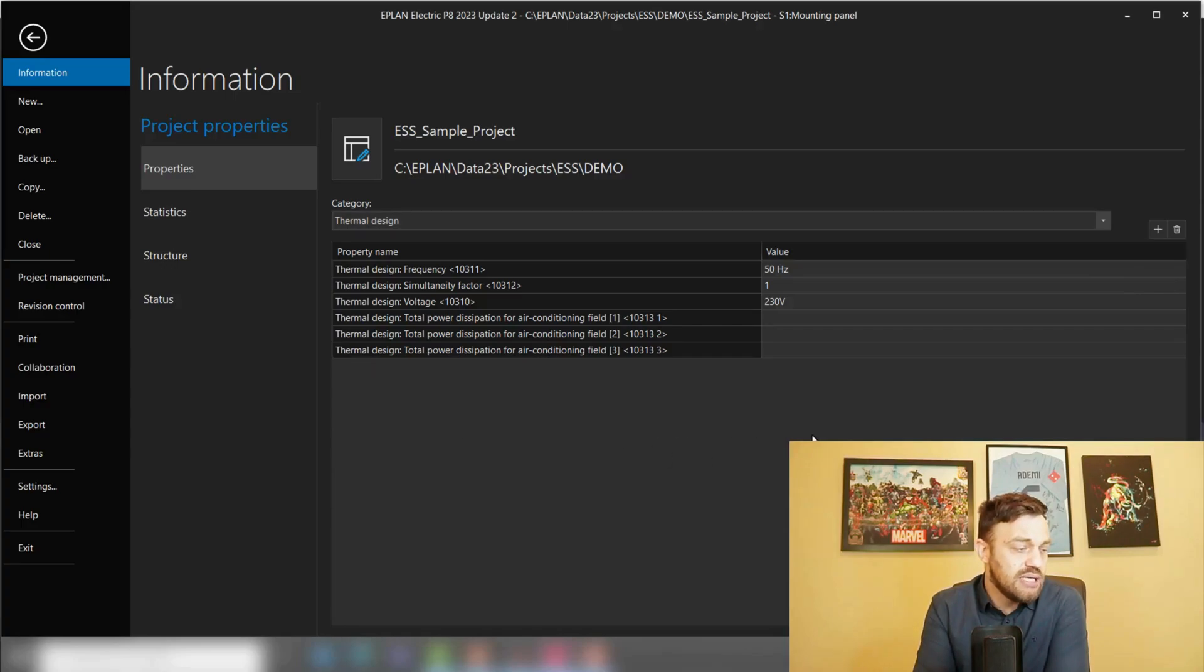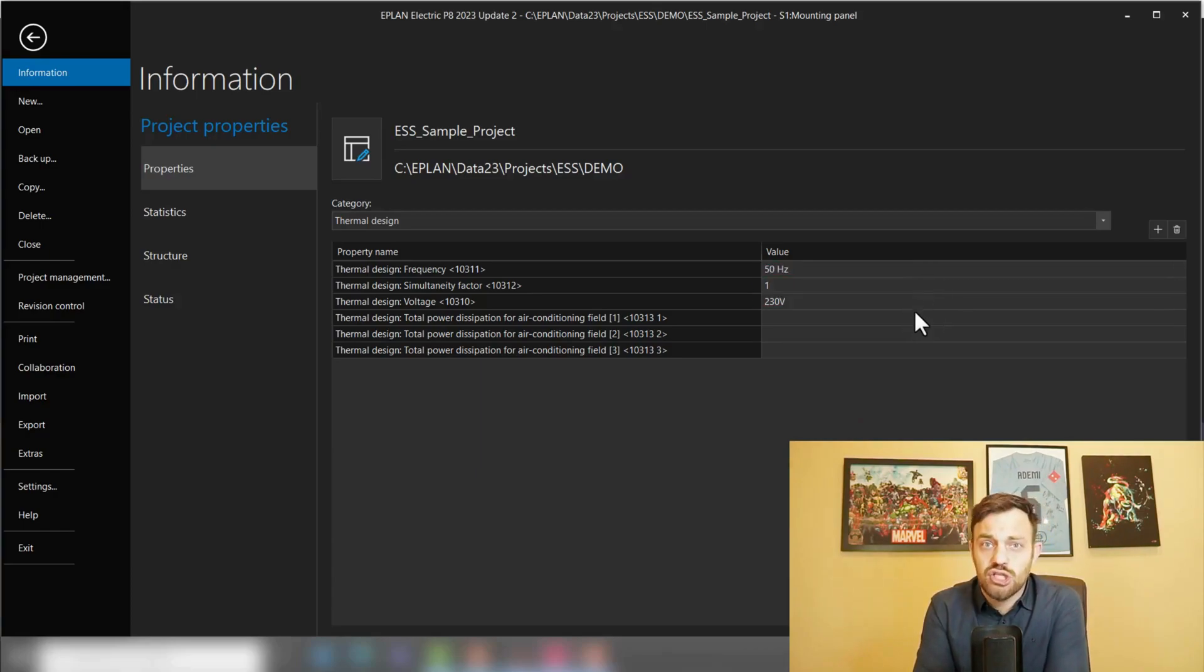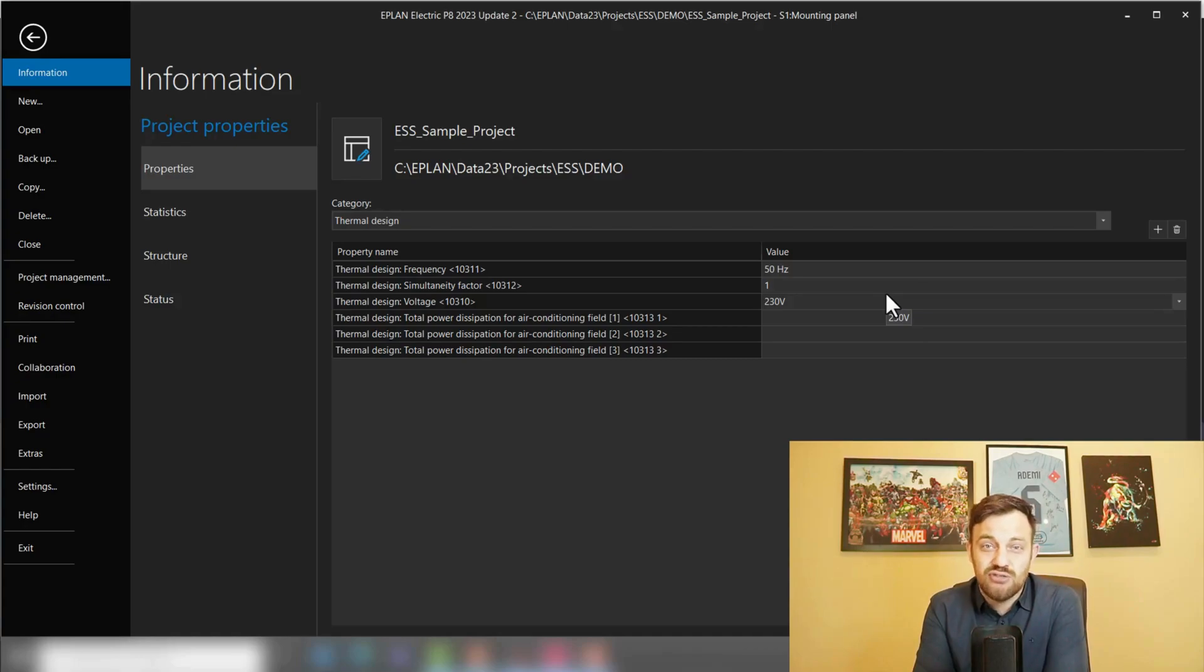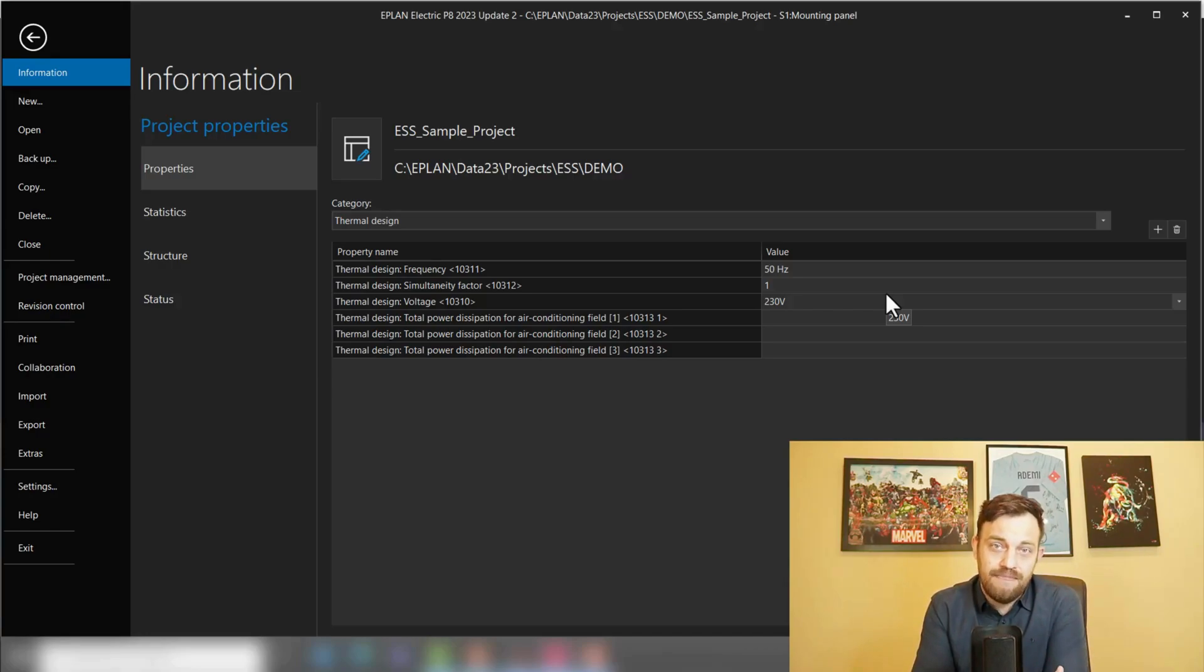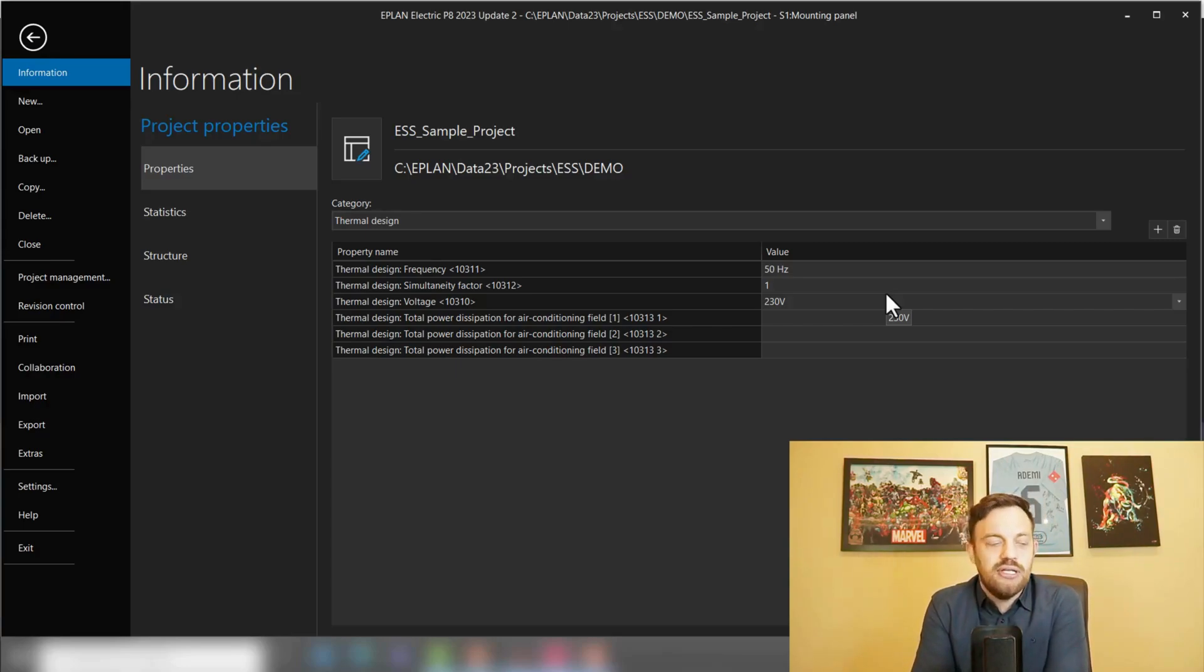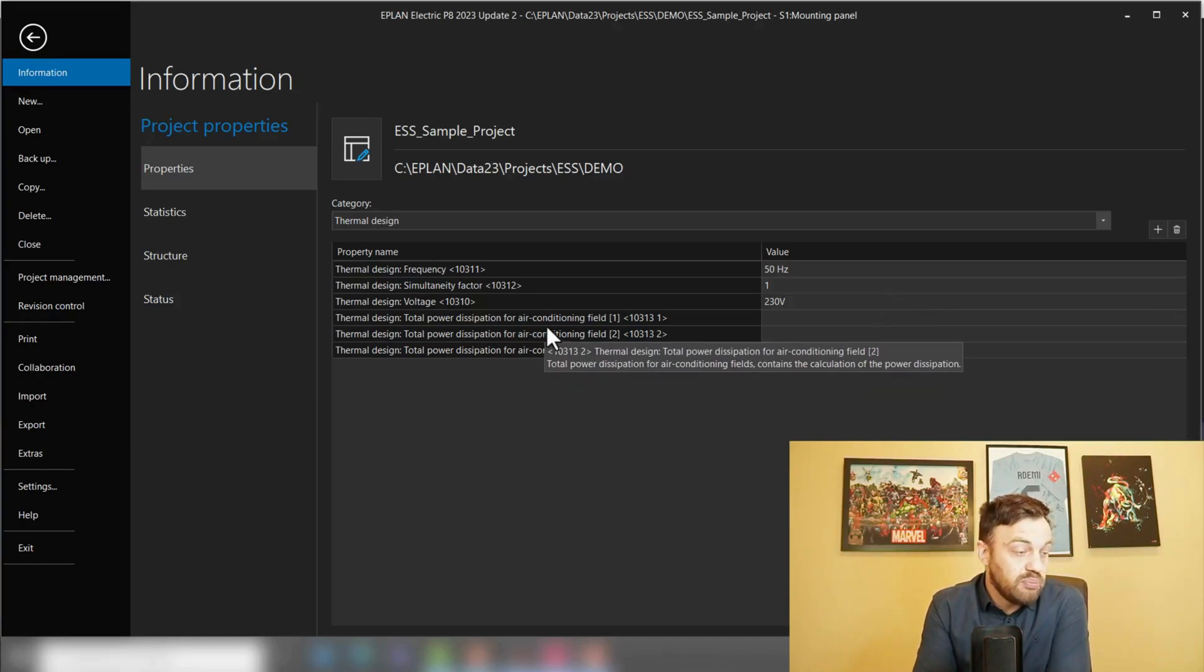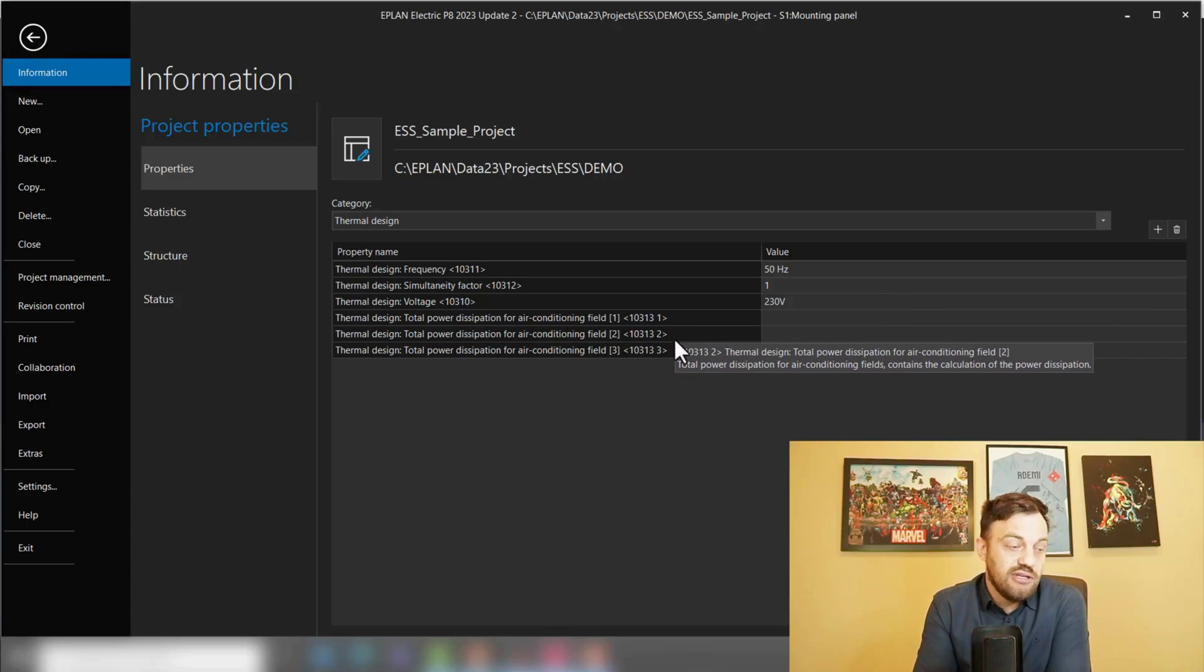EPLAN has prepared a special filter already for us. Here you can see now thermal design, frequency, simultaneity factor, and voltage. Frequency and voltage are self-explaining. The simultaneity factor is a number between zero and one where one stands for 100 percent of the components in the enclosure are powered at the same time. If 80 percent will be the case for your calculation, then you will need to enter a simultaneity factor of 0.8.